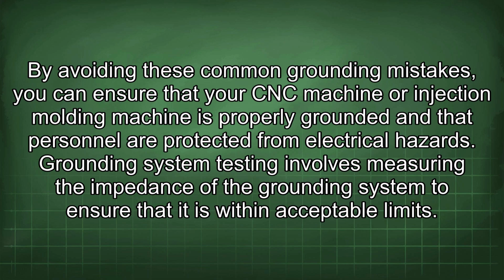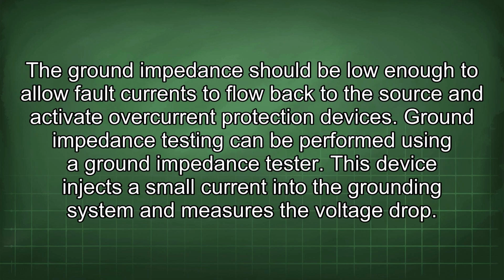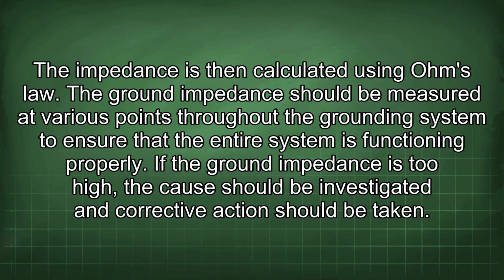Grounding system testing involves measuring the impedance of the grounding system to ensure that it is within acceptable limits. The ground impedance should be low enough to allow fault currents to flow back to the source and activate overcurrent protection devices. Ground impedance testing can be performed using a ground impedance tester. This device injects a small current into the grounding system and measures the voltage drop. The impedance is then calculated using Ohm's law. The ground impedance should be measured at various points throughout the grounding system to ensure that the entire system is functioning properly. If the ground impedance is too high, the cause should be investigated and corrective action should be taken.